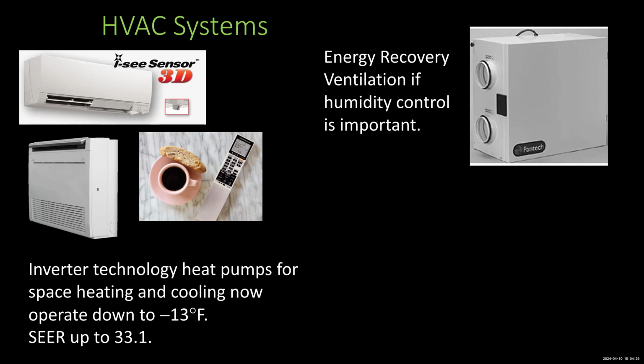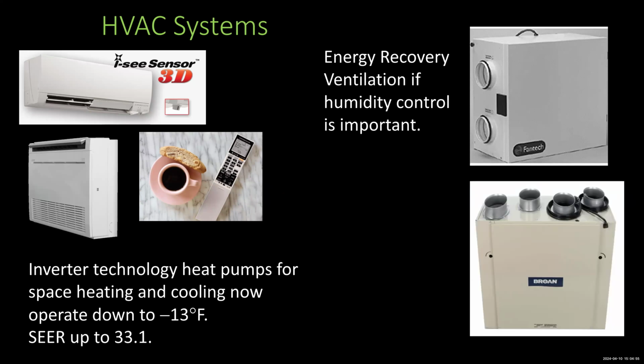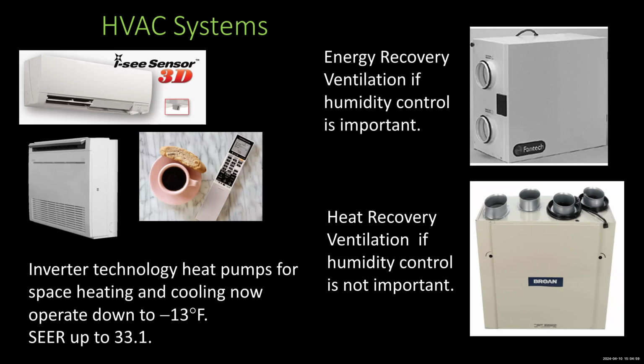It's called energy recovery ventilation. The efficiency on this thing is that you recover roughly 90% of the heat or cool that's being discharged to the outdoors with this unit. And that's compared to 0% recovery if it's coming in a crack in the window or a crack in the door or anyplace else. Okay, and here's the cousin of the energy recovery, the heat recovery. And this one happens to not have to worry about humidity, so it doesn't have to have a condensate drain. This is sensible heat only, which would probably be a little more applicable up north.